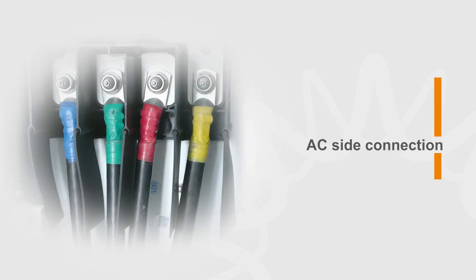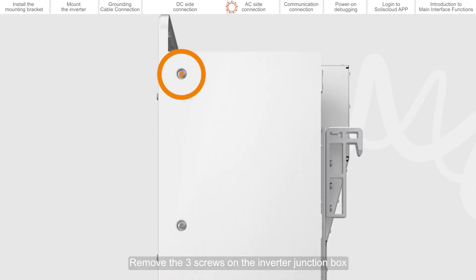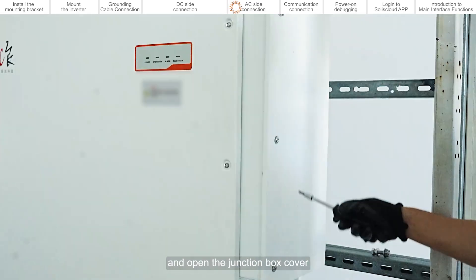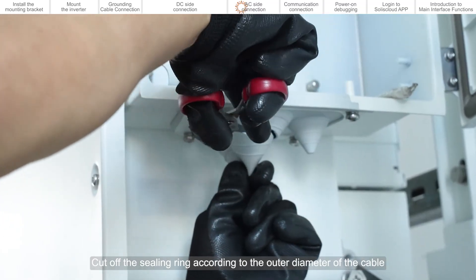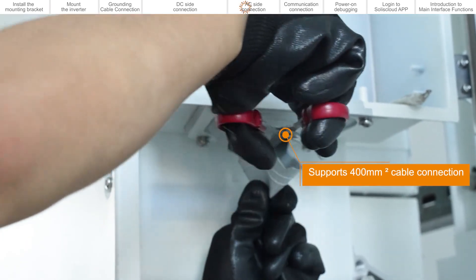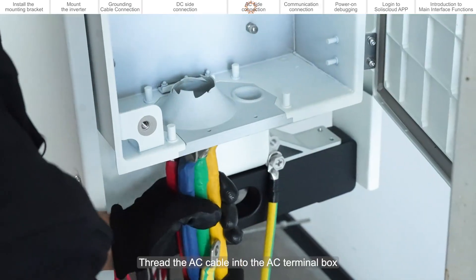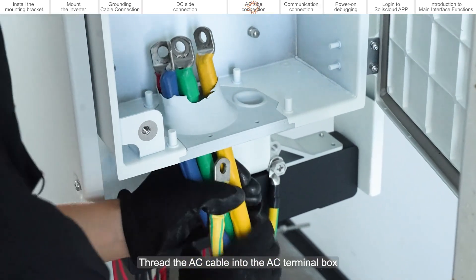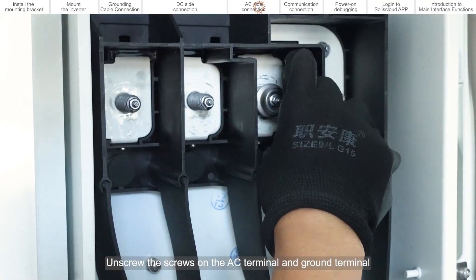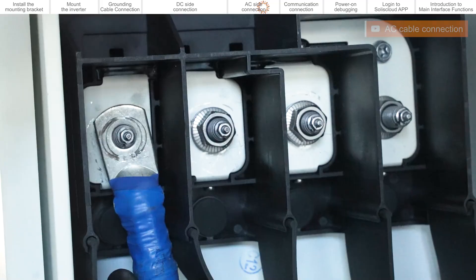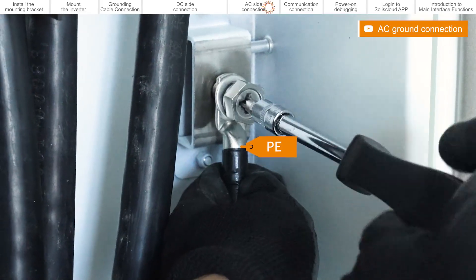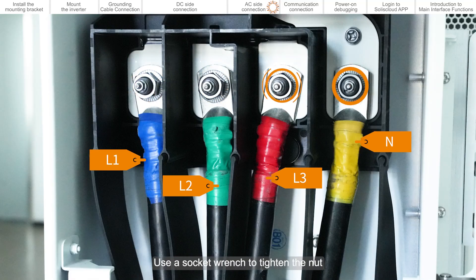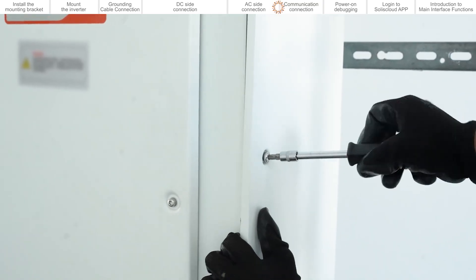AC side connection. Remove the three screws on the inverter junction box and open the junction box cover. Cut off the sealing ring according to the outer diameter of the cable. Thread the AC cable into the AC terminal box. Unscrew the screws on the AC terminal and ground terminal. Tighten the nut after the OT terminal installation is complete. Use a socket wrench to tighten the nut. Close the junction box and tighten the screws on the junction box.